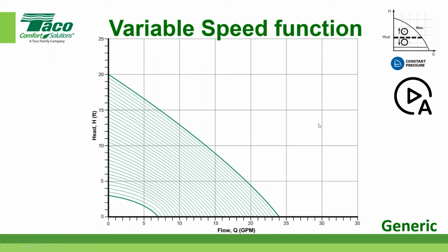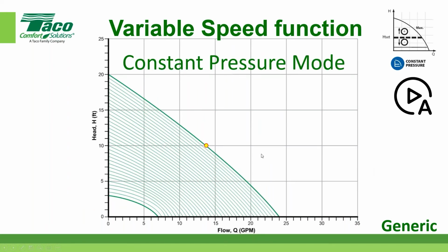Now let's look at the first automatic mode, and we'll call this flat one across here constant pressure. Let's put an operating point on there, and let's start closing valves. Watch the bouncing ball. It doesn't move in a flat line. It actually kind of hiccups. It goes up and then it comes back down, because of what you told it to do. You told it to stay, in this case, at 10 foot of head differential, and that's what it's going to do. As the valves close, it's going to slow down. Notice it's grabbing these incremental slower RPMs, but it's keeping an RPM high enough to maintain the resistance on the system, because it knows what it feels like based on the data logging that we put into the little chip within the circulator. Hopefully that makes sense to everyone.